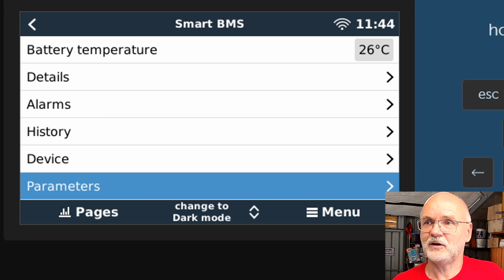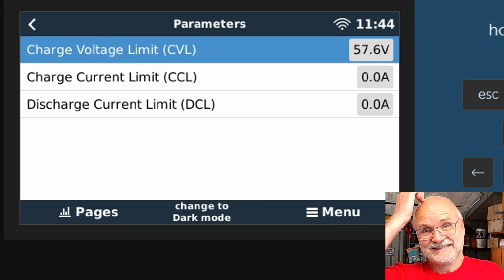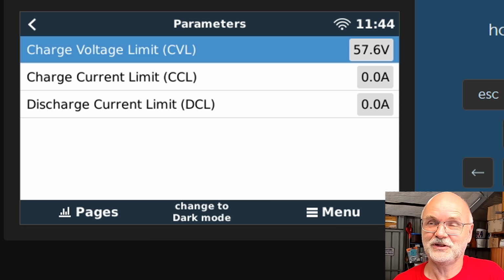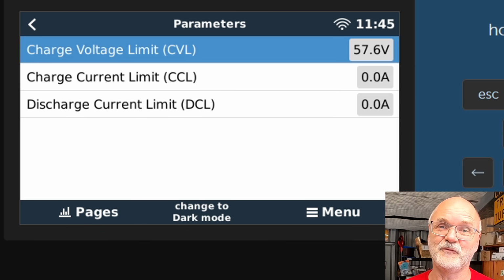Okay, let's go down to parameters and have a look. So what we can see here is the charge voltage limit, the charge current limit, and the discharge current limit. These are the main three parameters the BMS uses to control the charge into its battery. So in this case, it tells the inverter, or your charger, your MPPT, whatever, to charge to 57.6 volts, charge with a current of 0 amps, and discharge the battery with a current of 0 amps.